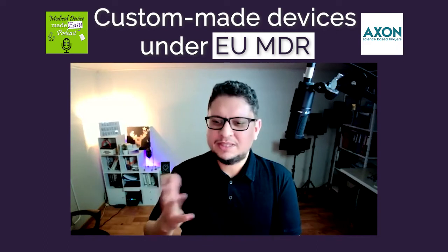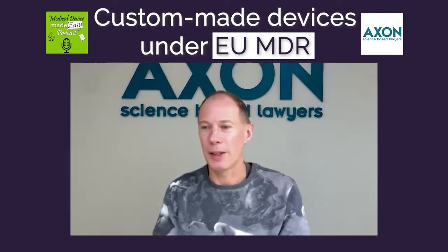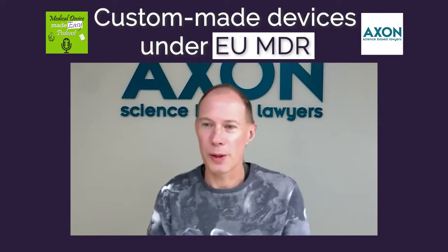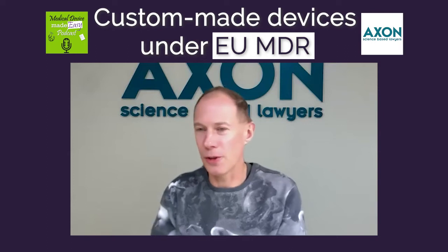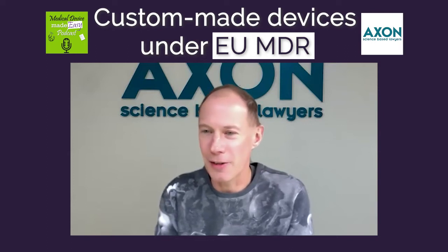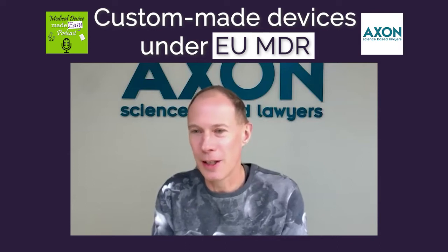So is there a reason for that? Yeah, it's because basically the way it works with custom-made devices is that under the MDD, you needed to do an Annex 8 declaration. Under the MDR, it's an Annex 13 declaration.